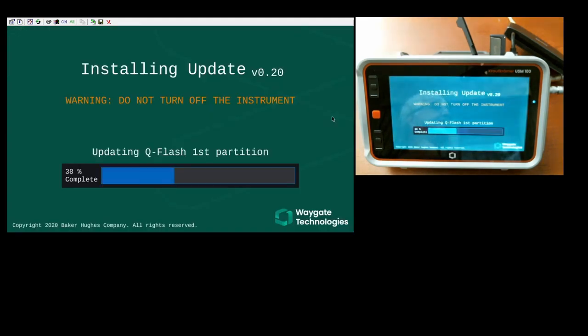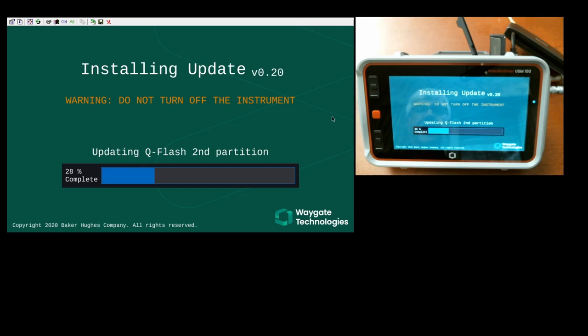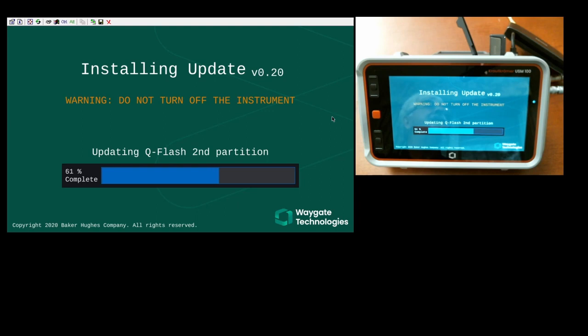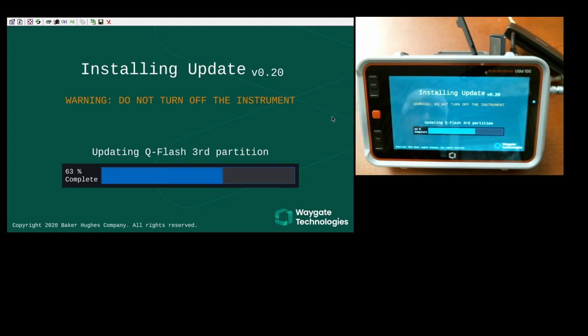Okay, now we see that the instrument has finished analyzing the update file. And it's begun the installation process. So you'll see the regular software closes. And the update installer begins to run. And there'll be a series of screens like this. So you'll see progress bar. It'll tell you that it's installing the update. It goes through several steps of this. There are many pieces of memory to update in the instrument, along with the main hard drive. So this process generally takes 10 to 15 minutes to complete. Again, we're going to speed through this section, cut some time out and accelerate things. And we'll catch up here in about 15 minutes.